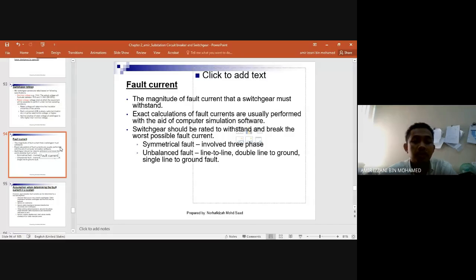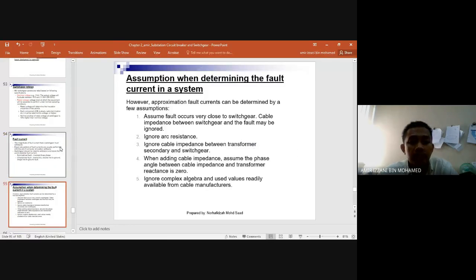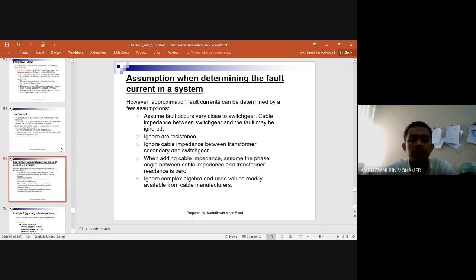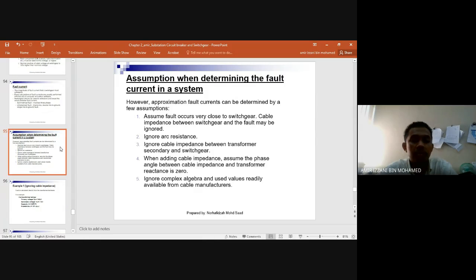This is the explanation on fault current. Okay, how do we determine the fault current in a system? There are a few assumptions that we can use. The first one is to assume the fault occurs very close to the switchgear. Cable impedance between switchgear and the fault may be ignored.